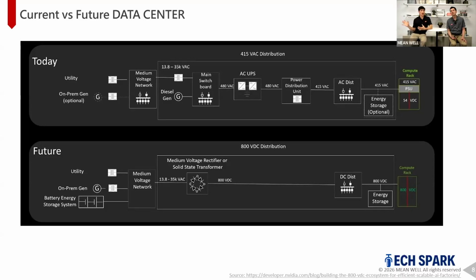So what NVIDIA has announced, going off their public announcement, is that they're transitioning into this high voltage DC infrastructure. What that means is they're stepping down that high 13 to 35 kilovolt AC power directly to 800 volts DC, and they're doing that through the use of a solid state transformer.